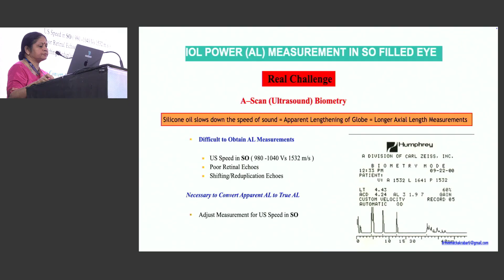Then again, when you're doing the scan, you see that the retinal echoes, which are supposed to be highly reflective, become shorter echoes. There are poor retinal echoes. And if you're dealing with an eye which has emulsified silicone oil, there are multiple reduplication echoes in the baseline. All this makes correct calculation of the axial length quite difficult. So in this situation, it is necessary to convert the apparent axial length into the true axial length, making adjustments for the ultrasound speed in silicone oil.